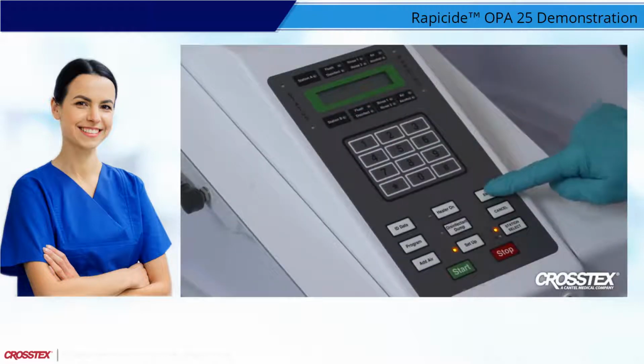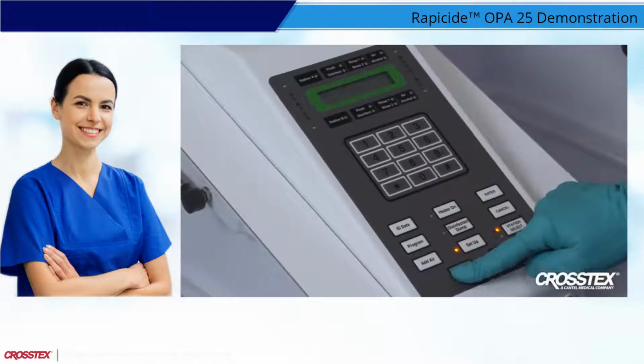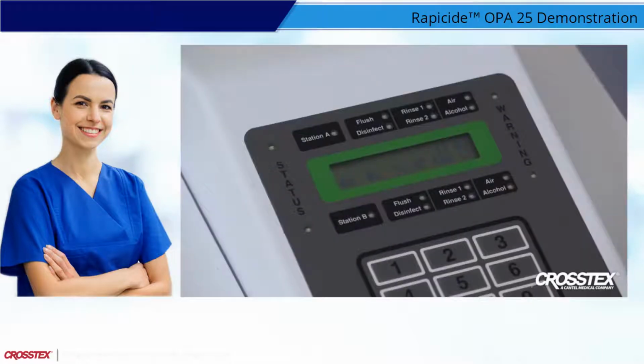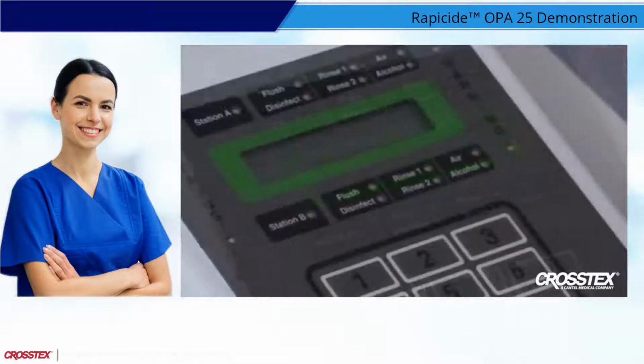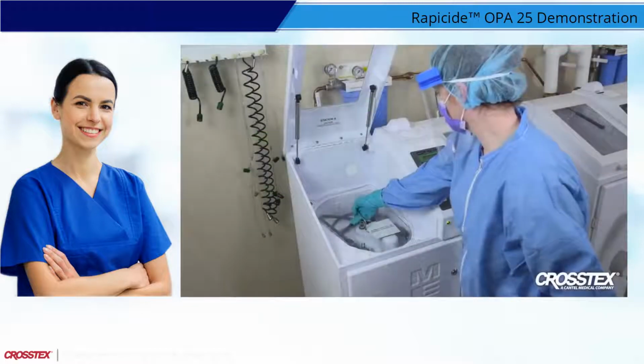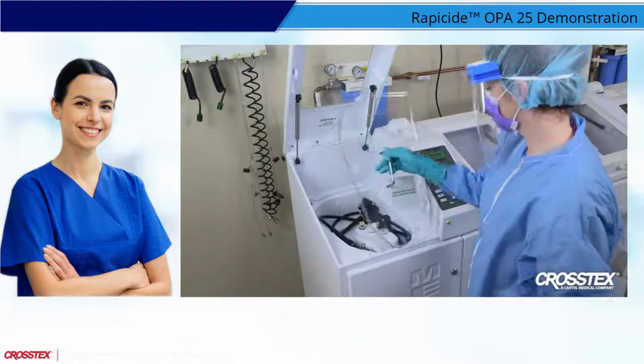Perform the automated disinfection cycle in accordance with the AER manufacturer's IFU. Be sure to select a cycle that has been validated for use with OPA-based disinfectants and the scope manufacturer's IFU. When the cycle is complete, verify that the stop LED is illuminated before opening the lid and removing the scope.